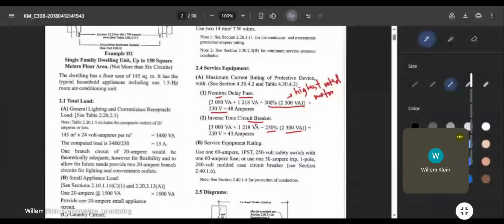Now on your design, the circuit breaker will be required, of course. For the fuse, it's optional. So if you want to include the computation or the inclusion of the fuse rating, for example, after computation it's mentioned what you will use: 60 ampere, 250 volt safety switch. This is single pole, single throw, which means one time use, of course. Your fuse is just one time use. And 50 ampere trip, single pole, 240 volt molded case circuit breaker. If it's optional to you, you can just include the circuit breaker part. So just be familiar with the computation of the fuse, but in your design you can just include the circuit breaker, especially on the schedule of loads.